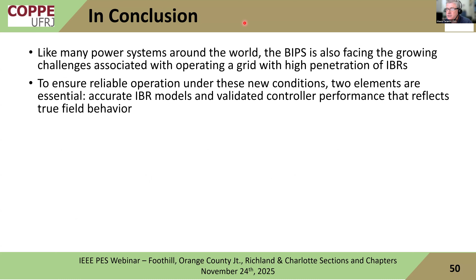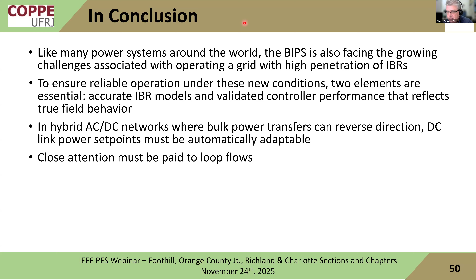To ensure reliable operation under these new conditions, two elements are essential: accurate IBR models and validated controller performance that reflects true field behavior. In hybrid AC-DC networks where bulk power transfers can reverse direction, DC-link power set points must be automatically adaptable. Close attention must be paid to the loop flows.